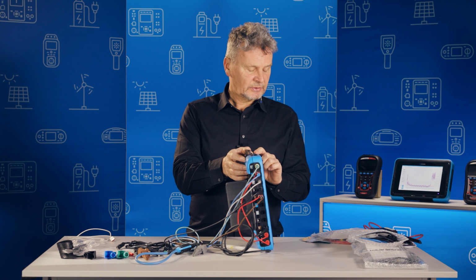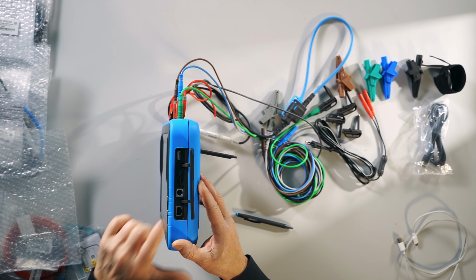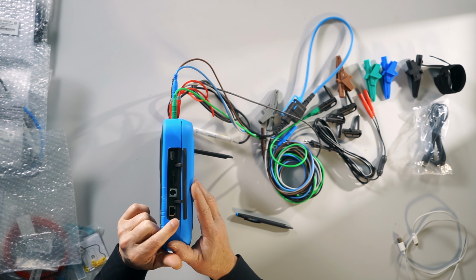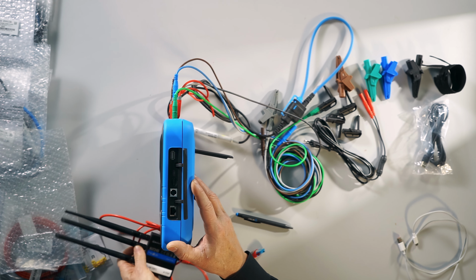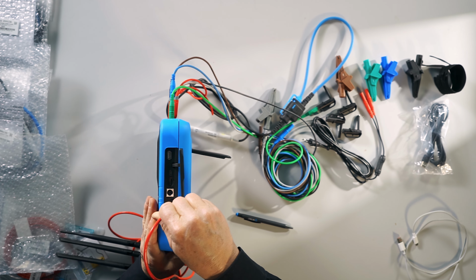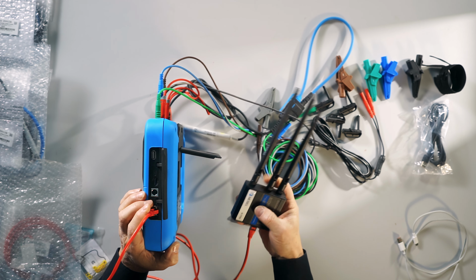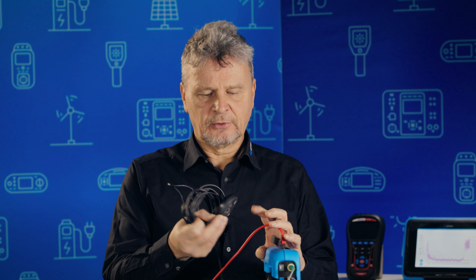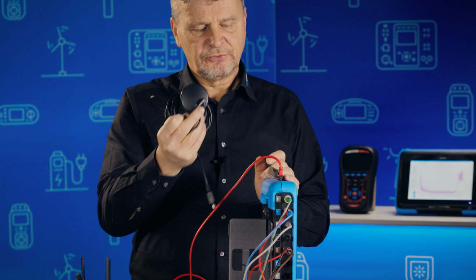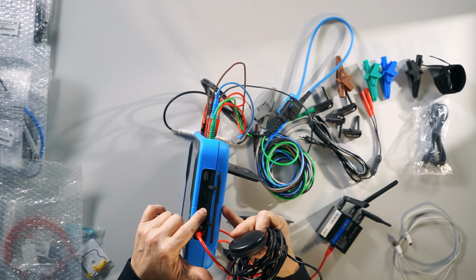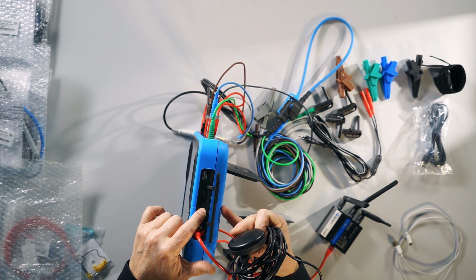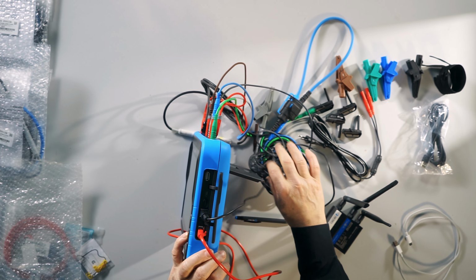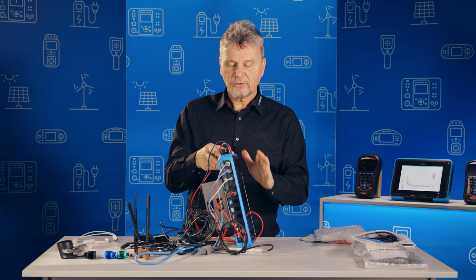Then we have an Ethernet port, which is for remote connection to the instrument via VNC or via the software MP Vision. You can connect it directly to a LAN interface if you have a LAN network at your testing place, or you can connect to an external modem for downloading the data, or connect directly to the instrument via VNC. There is also a PS2 port for connecting a GPS receiver, which is used for synchronization of the actual time in the instrument, and also for getting the GPS location of the measurement place. So all data are attached and saved safely inside the instrument.